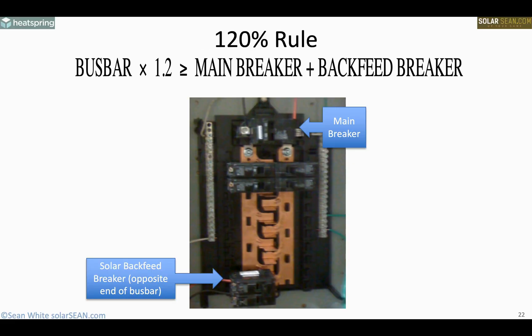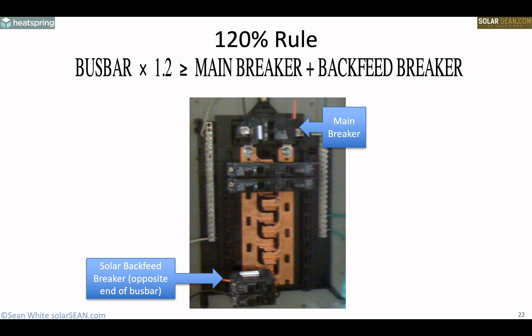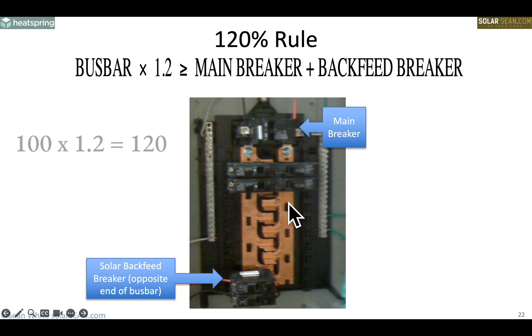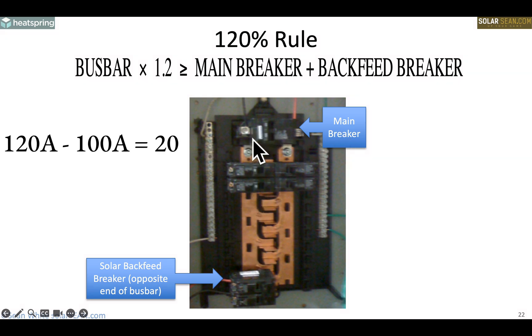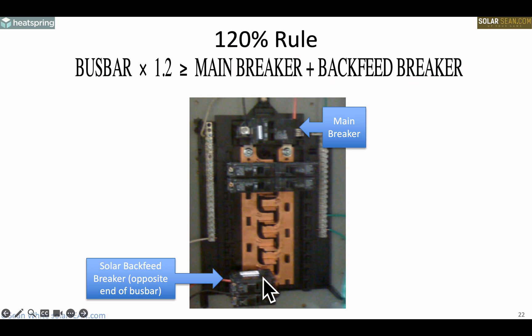And in the beginning, there was code. Here's something from Article 705, Section 705.12 of the National Electrical Code. If you want to do a simple installation: here's your main breaker, and this is called the bus bar — it's where you connect your breakers. If my bus bar is rated at 100 amps, I do 100 times 1.2 equals 120. Then subtract the 100-amp main breaker rating, and I get 20 amps left over for the largest solar backfeed breaker — placed at the opposite end of the bus bar. That is called the 120% rule.